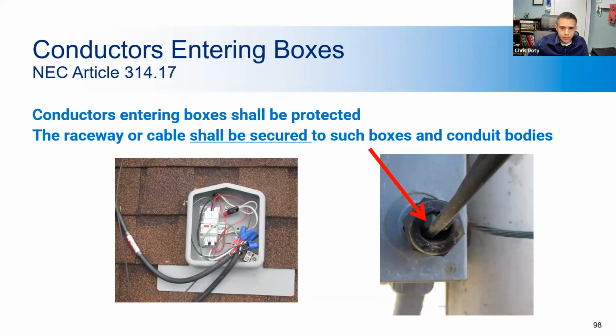So another common error is where the fittings used for conductors to enter an enclosure are missing or not installed to secure the conductors from movement. And that'll cause stress on the terminations. So on the right, the hole in the strain connector is too big for the cable, so it would fail. That would essentially do nothing to prevent these from moving all over and eventually eroding away and having stress on the terminations. So that would have to be switched out for a tighter connection.